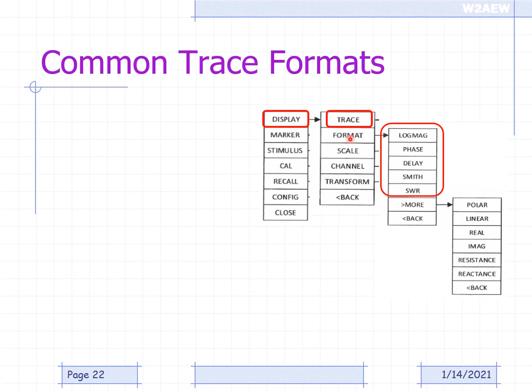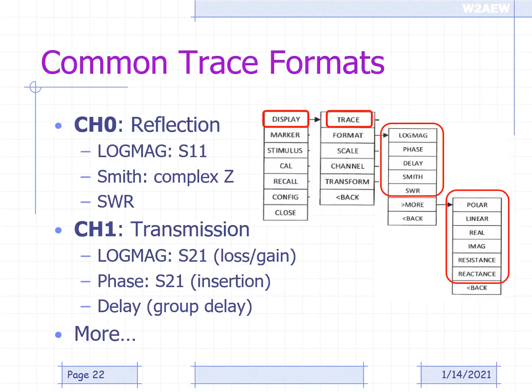Common trace formats are typically shown here. You go to display trace, then select format. For the channel 0 measurements, you're most often using either log mag for S11, or a Smith chart to look at complex impedance, or selecting SWR. For the channel 1 measurements, again, it's typically log mag for the loss and gain measurements. Then you've got phase measurements, which are typically going to be linear, and the delay measurements are typically linear as well. And there are other additional measurements available here for more advanced applications, but there are a lot of other ways to display the same data. It's all just mathematically related. Setting the source or the stimulus is setting the frequency range you're going to make a measurement over. And you basically pick whichever is easier.